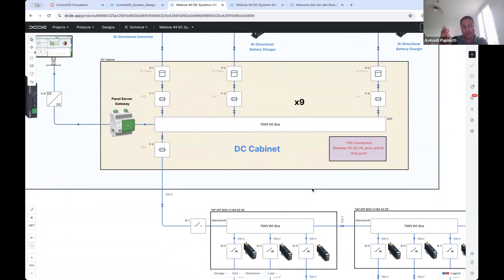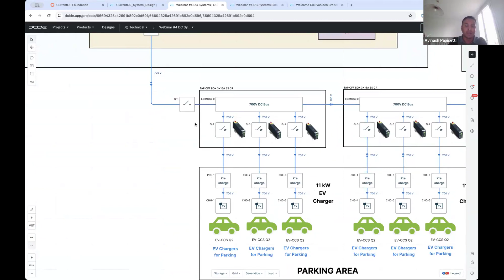Similarly, further down, we have extended the bus outside. Outside, whether on cable or on a busway, I have tap-offs protected by solid state breakers, which we call current routers. Each breaker is protecting an EV charger, which is nothing but a DC-DC converter. So this is, in a nutshell, the entire concept.